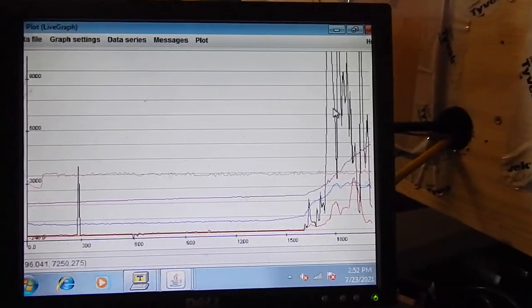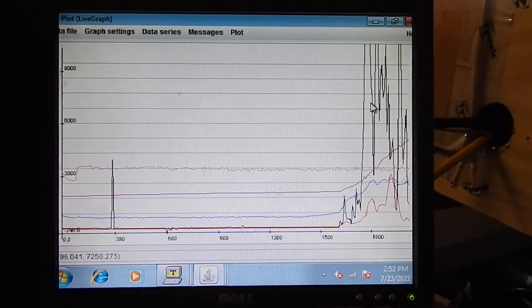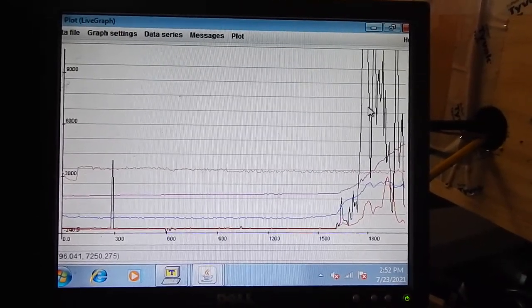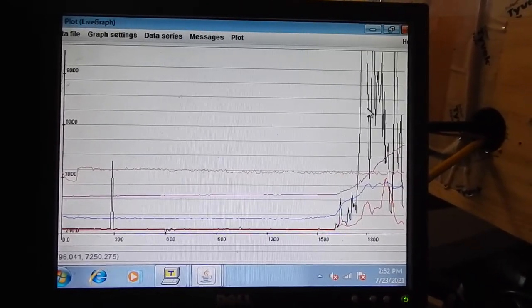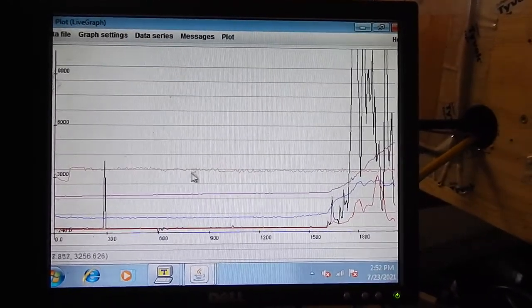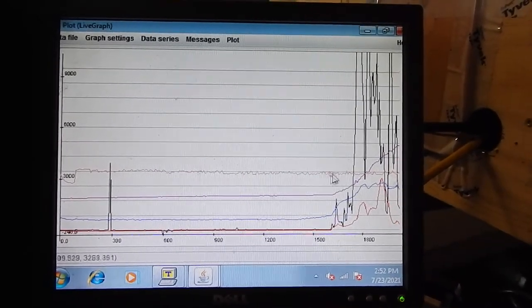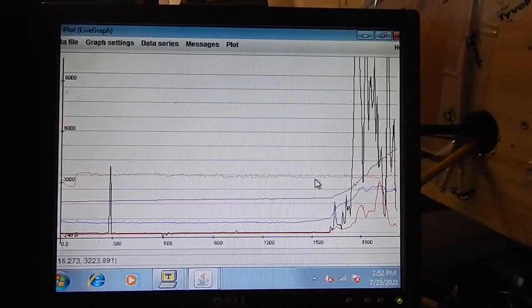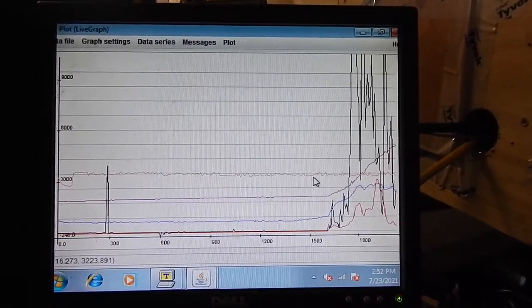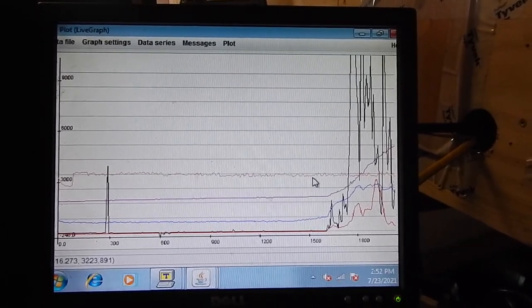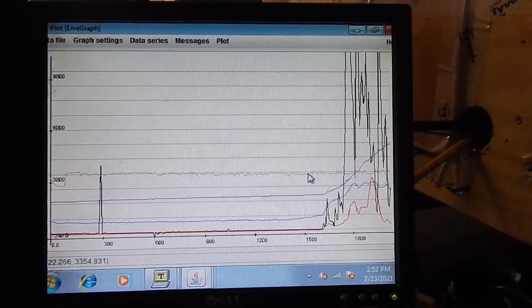For particulate matter, we have to make sure to load the filter high enough and same thing, we can't plug the filter. We're also measuring the flow rate through the filter and we're doing that digitally so we can watch for whether or not the filter is plugged.